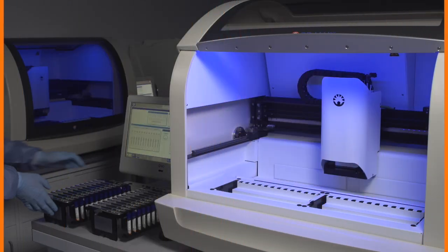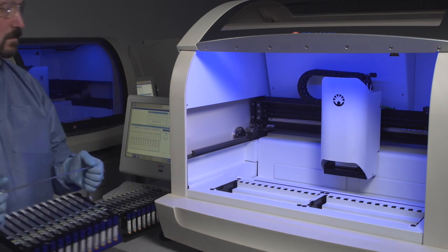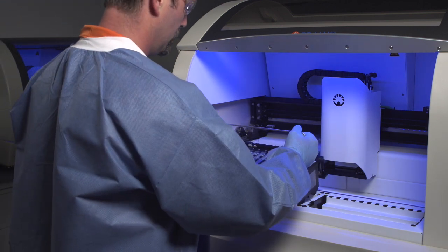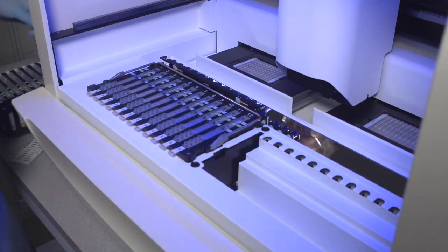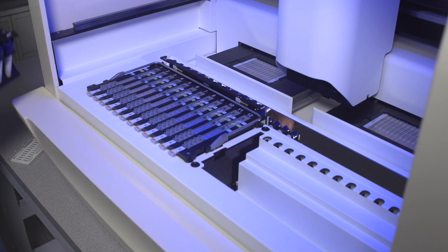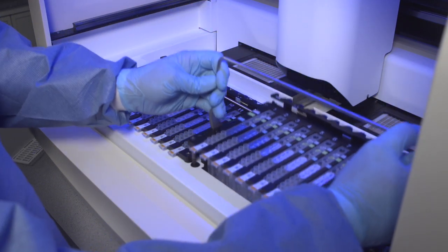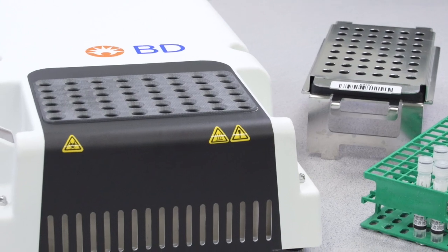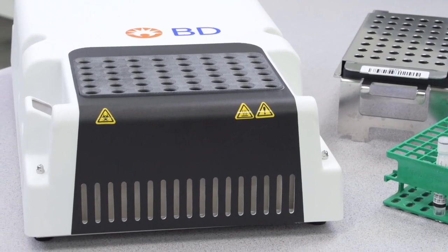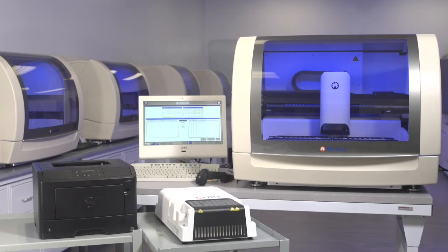The only sample racks the instrument will accept are BD Max system sample racks. Each rack holds up to 12 samples and the reagents needed to test them. The system includes 4 of these racks as well as an optional pre-warm heater and rack. The BD Max system will accept up to 2 racks for each run.